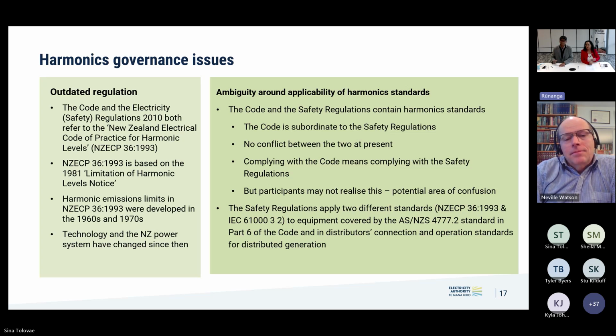The second key thing is the ambiguity in the applicability of the harmonic standards. NZECP 36 is the primary standard used across several utilities in New Zealand. If they adhere to or comply with the code, they comply with the safety regulations, because the code is subordinate to the safety regulation. At present there's no conflict.